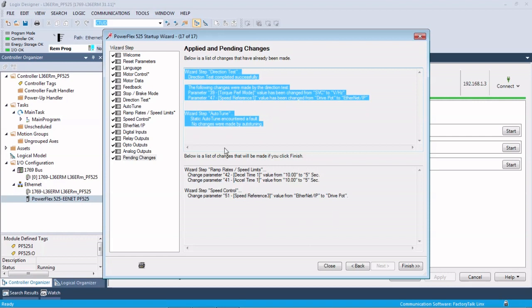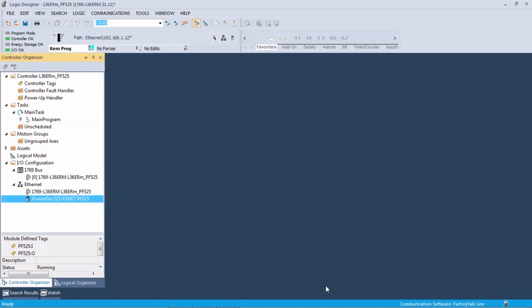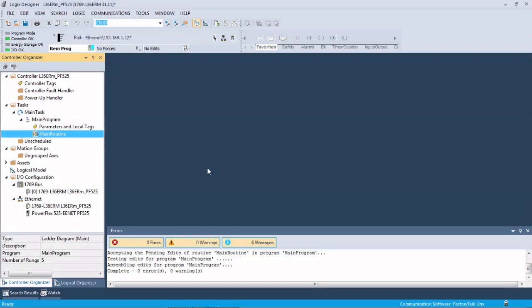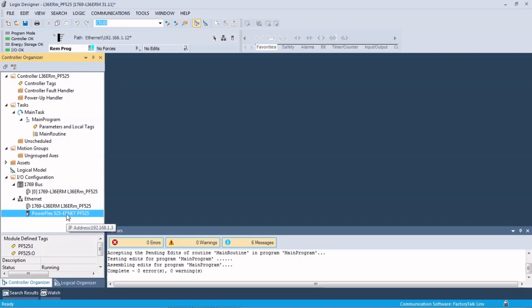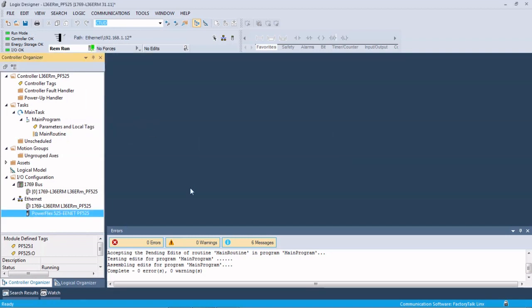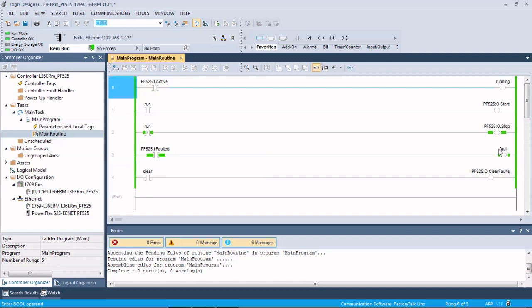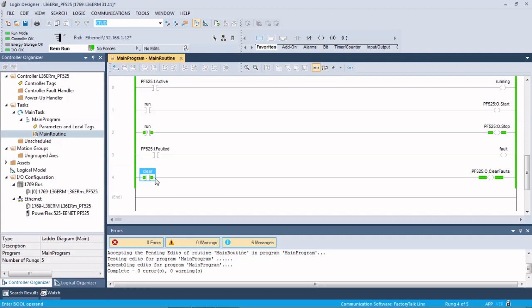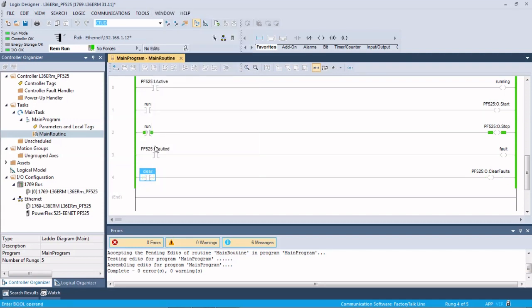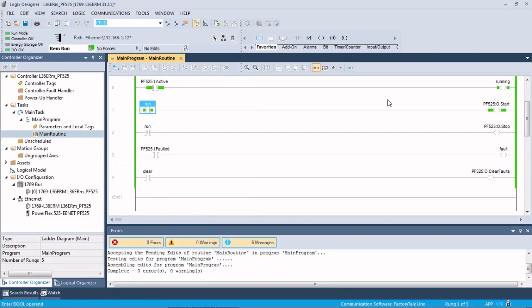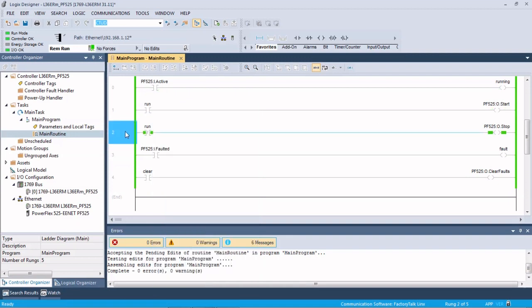There's our list of pending changes, and we're going to go ahead and hit finish on this and OK. So that's it. We just went through a startup wizard on a drive. So now what we're ready to do is we can go ahead and put your controller back into run mode. And I put in some simple logic here. As you can see, the drive is faulted. We have a fault on the drive, so we're going to toggle the clear to send our clear faults out. OK. Our fault went away. Now we should be able to start our drive. And it's running. And we stopped it. So there you go, that's how you set up and go through a drive startup through Logix.